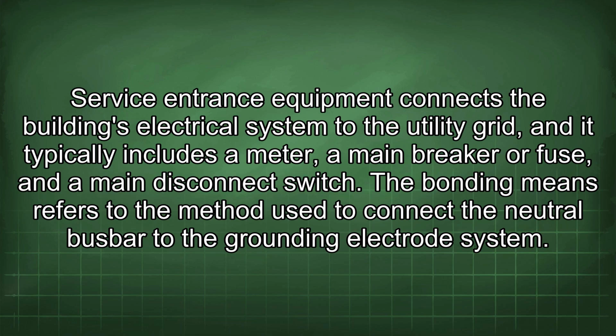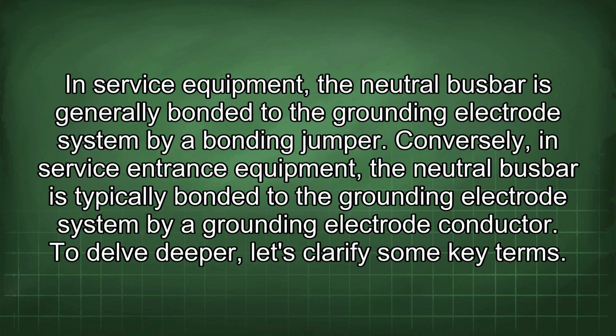The bonding means refers to the method used to connect the neutral busbar to the grounding electrode system. In service equipment, the neutral busbar is generally bonded to the grounding electrode system by a bonding jumper. Conversely, in service entrance equipment, the neutral busbar is typically bonded to the grounding electrode system by a grounding electrode conductor. To delve deeper, let's clarify some key terms.